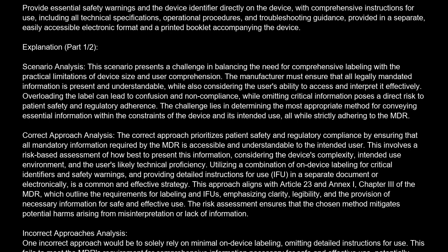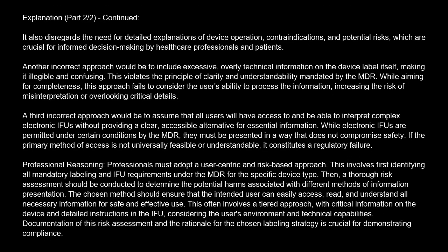Incorrect approaches analysis. One incorrect approach would be to solely rely on minimal on-device labeling, omitting detailed instructions for use. This fails to meet the MDR's requirement for comprehensive information necessary for safe and effective use, potentially leading to user error and adverse events. It also disregards the need for detailed explanations of device operation, contraindications, and potential risks, which are crucial for informed decision-making by healthcare professionals and patients.